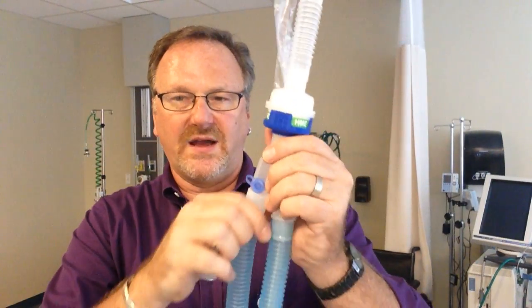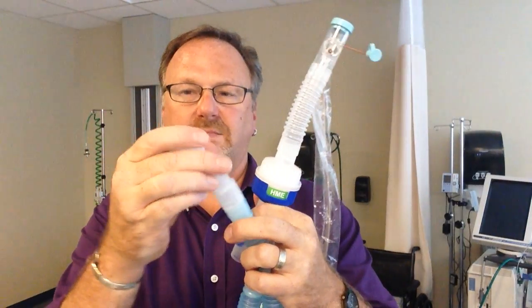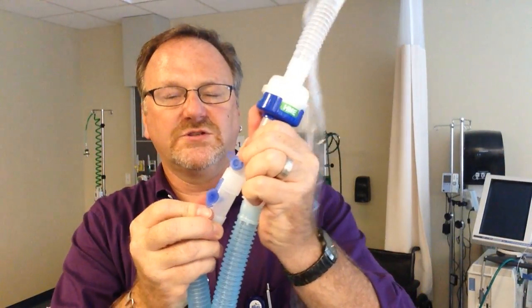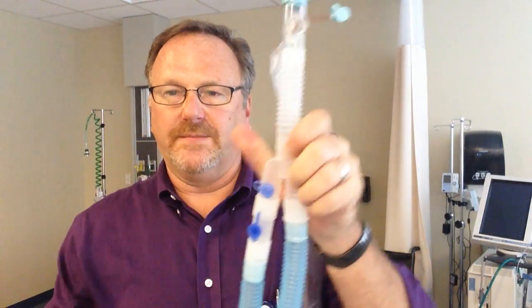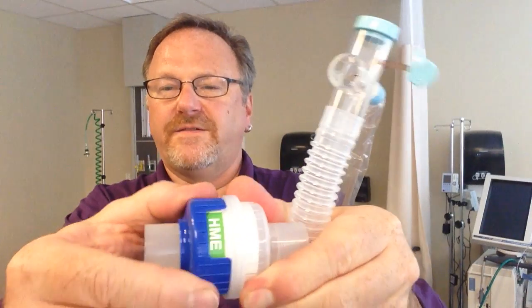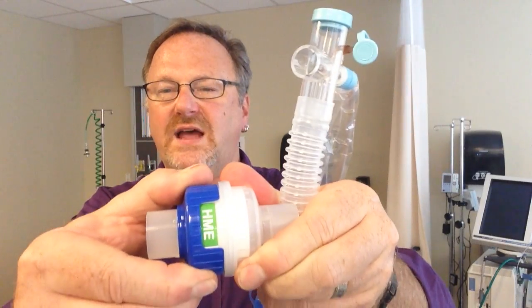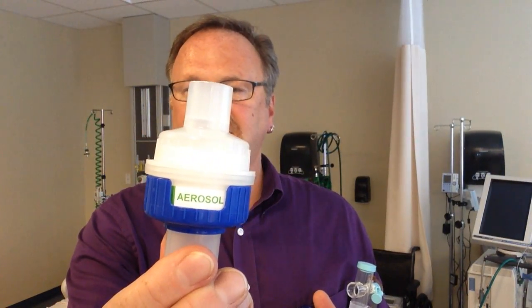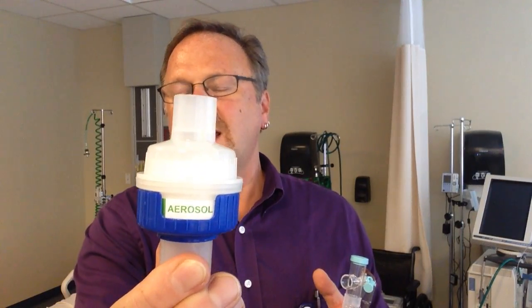Now if I wanted to give an MDI, there are adapters that I can use and put them in line so I do not constantly have to break my circuit. That would go there, just like that. The next thing I need to do, if I'm using the circuit, is to remove my HME. Yes, some HMEs have aerosol or a bypass and an HME. Many hospitals do not use ones like this, so we want to get you in the habit of taking them out. The other disadvantage is that using HMEs like this, that bypass the HME process, many therapists forget to turn it back on to HME. So the patient is just lying there breathing dry air.